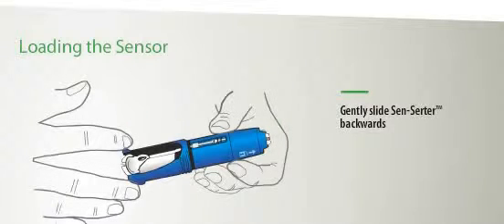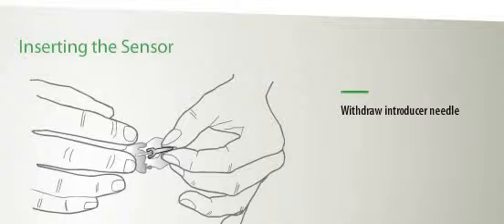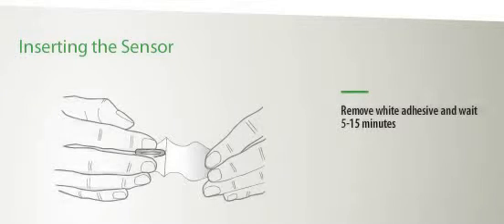To remove the Sen-Serter, gently slide it backwards with the feet still touching your skin. Gently withdraw the introducer needle at the same angle that you inserted it. Lastly, remove the white adhesive film and gently rub on the adhesive. Wait 5 to 15 minutes until the sensor is wet with interstitial fluid before you connect your MiniLink transmitter.